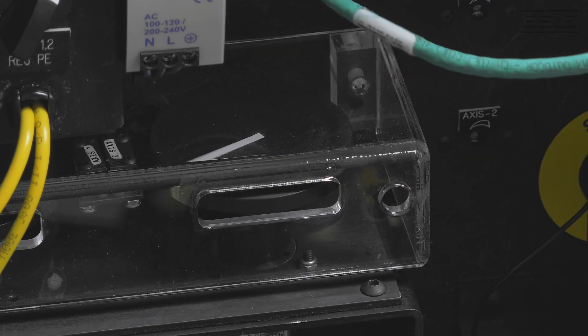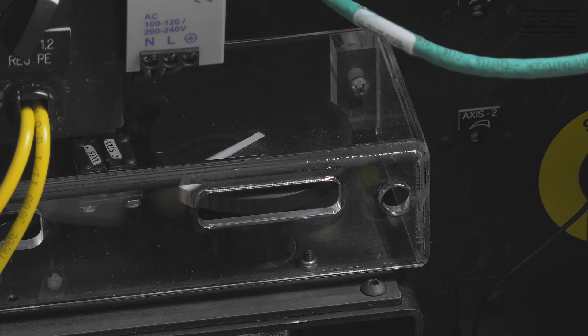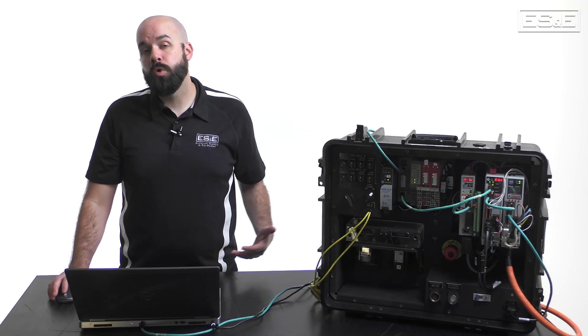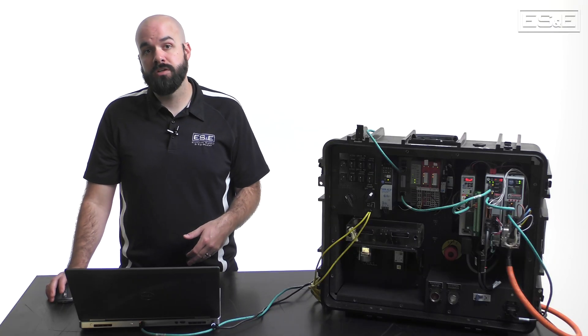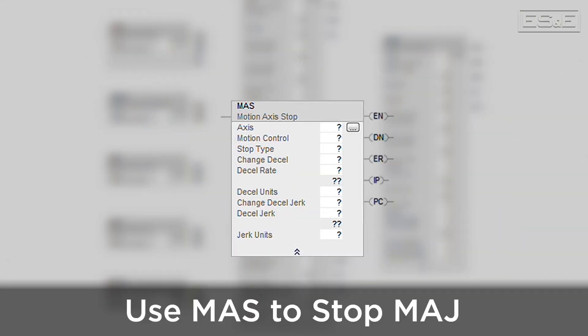When the MAJ is executed, the motor being controlled by the target axis will ramp up to speed using the defined parameters until it reaches the target speed. When the target speed is reached, the motor will remain at that speed indefinitely. Usually an MAS or motion axis stop instruction will be used to stop an MAJ. This MAS will need to be set to a stop type of ALL or a stop type of JOG.